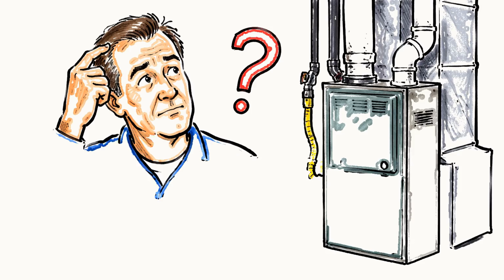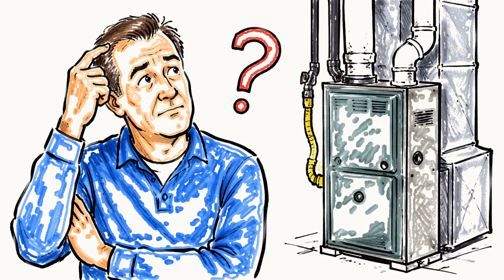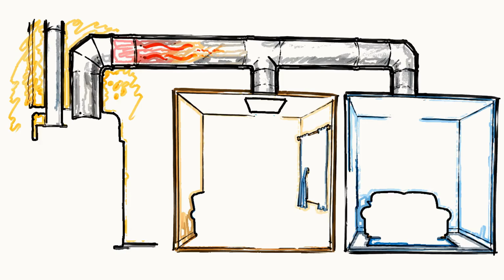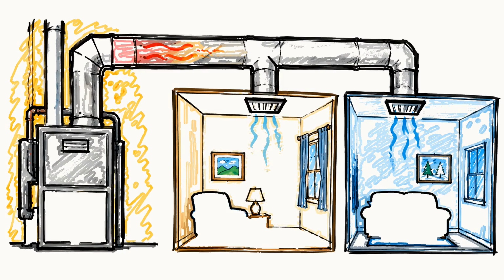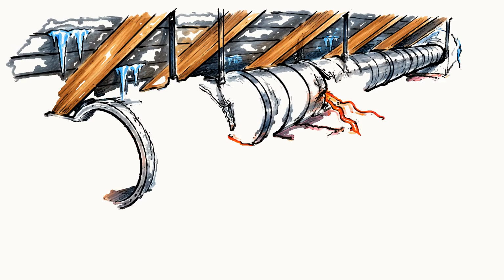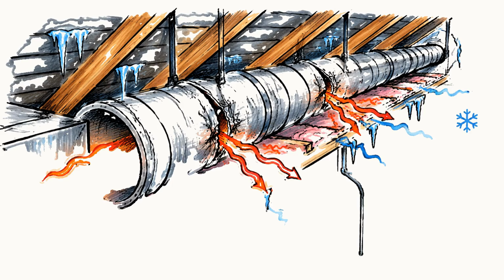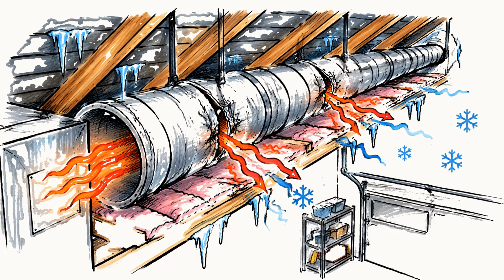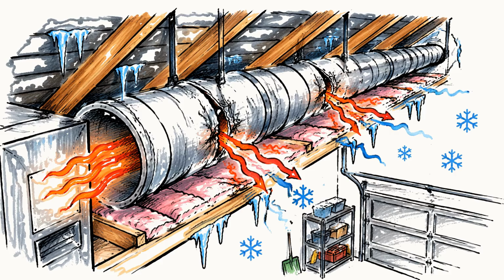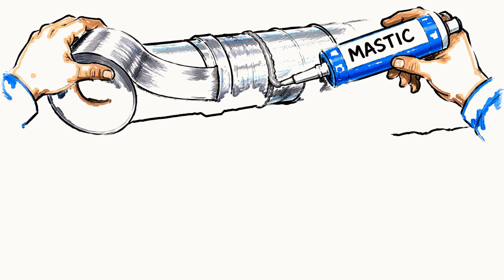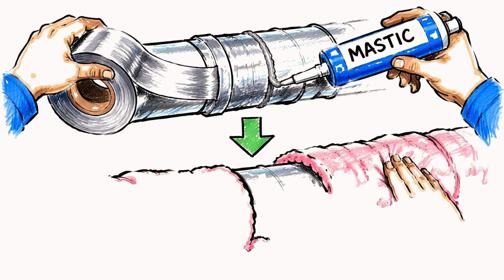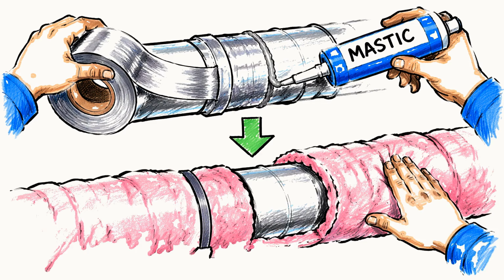One last scenario that confuses people. Sometimes the air is genuinely warm right at the furnace but arrives cold or lukewarm in the far rooms. That is usually leaky or uninsulated ductwork running through a freezing attic, crawl space, or garage, bleeding the heat out before it reaches you. Sealing the joints you can reach with foil tape or mastic, and wrapping the ducts in cold spaces with insulation takes care of that one.